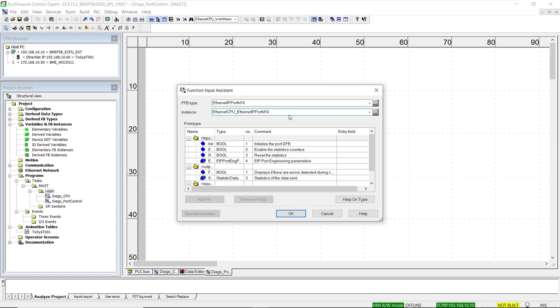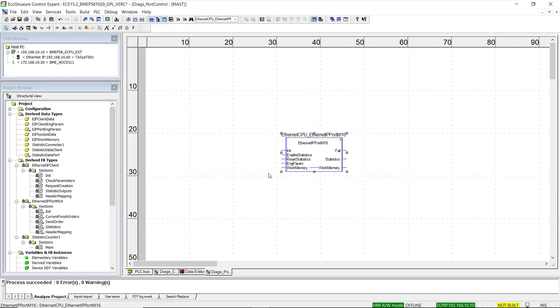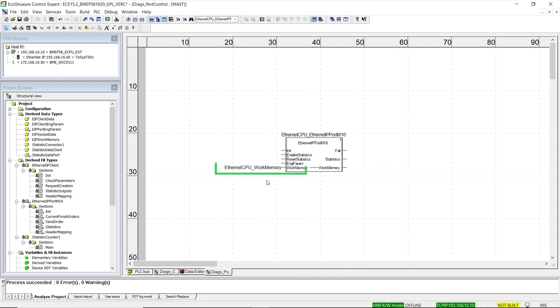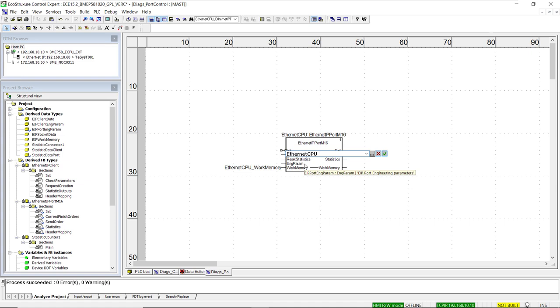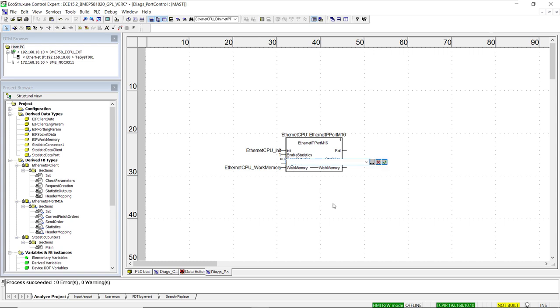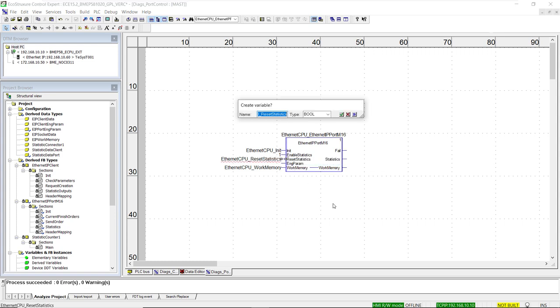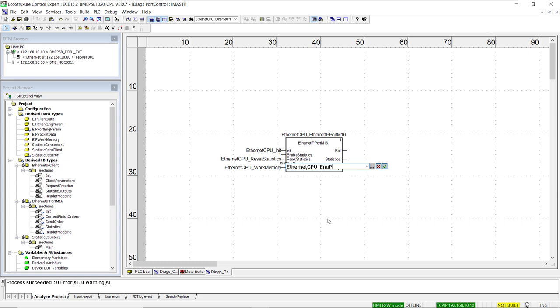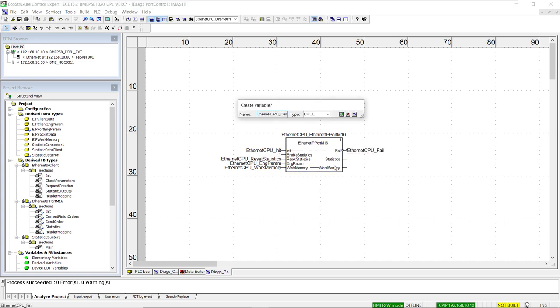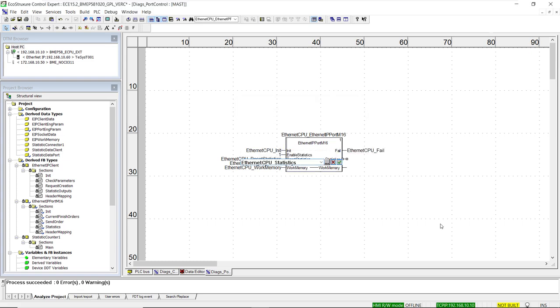We give a name to the instance following best practices: a prefix followed by underscore and the function block name. We add to the bottom-left input pin the exact same work memory variable name used for all client function blocks linked to this port function block. We then continue creating variables for each input and output, using the prefix ethernet CPU followed by underscore and the name of the input or output pin as displayed in the function block.